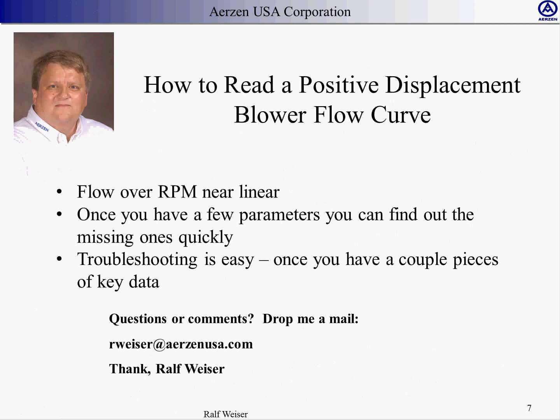Troubleshooting is therefore easy because once you have the units of measure correct, you have a flow curve off that machine and a couple of key parameters — you can figure out what is going on with the machine. Is it too slow? Is it too fast? What other things could be happening? If the clearances go up, so does the temperature and the flow drops. The key is once you can plot a couple of these data points off the flow curve, you can extrapolate what you can expect. Measurement and the accuracy of that measurement is the key. That in all is very quickly what you can do and how you need to do flow calculations on blower curves.